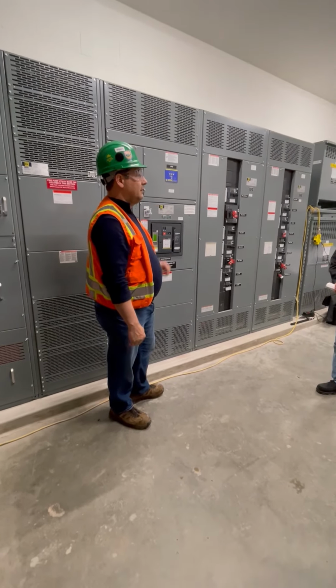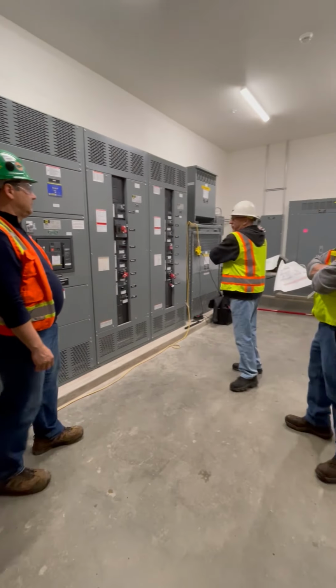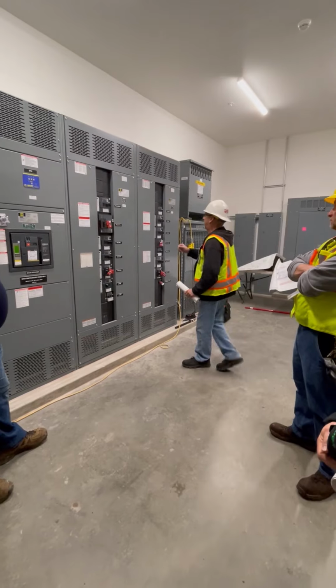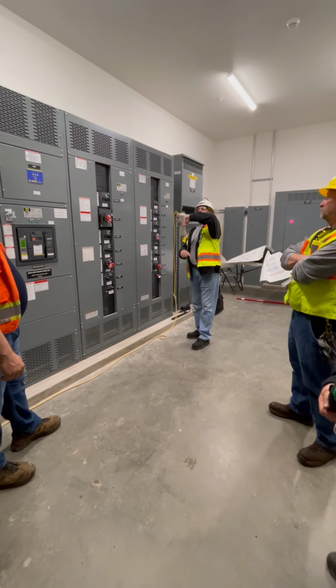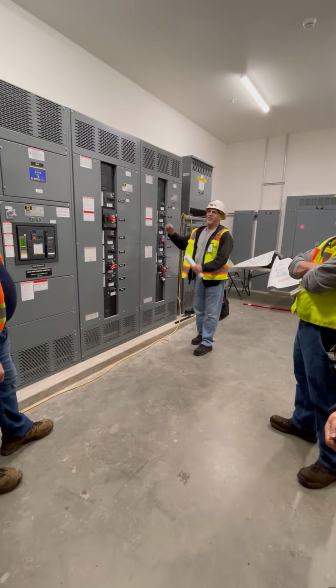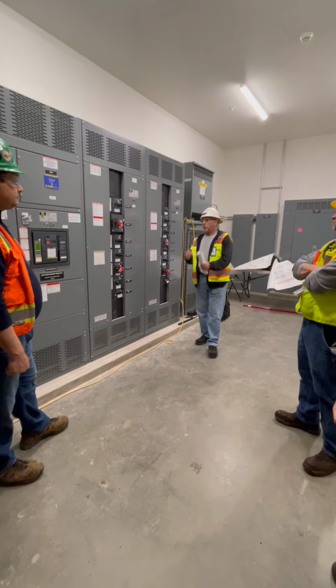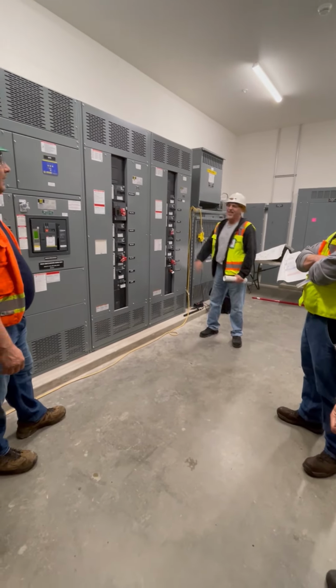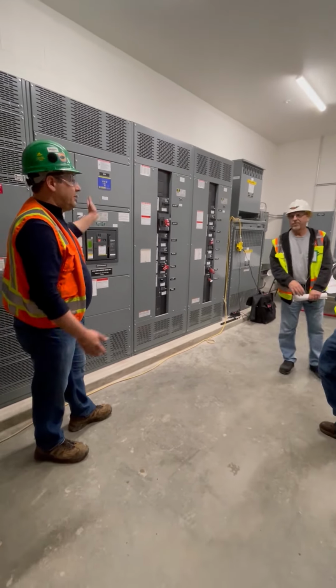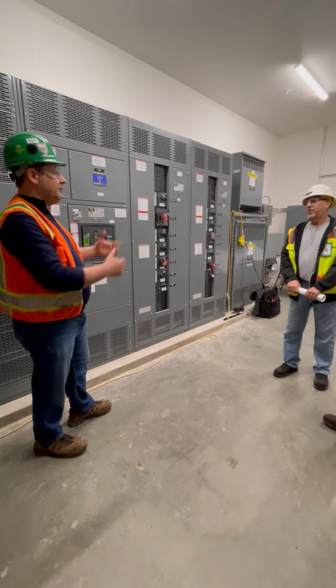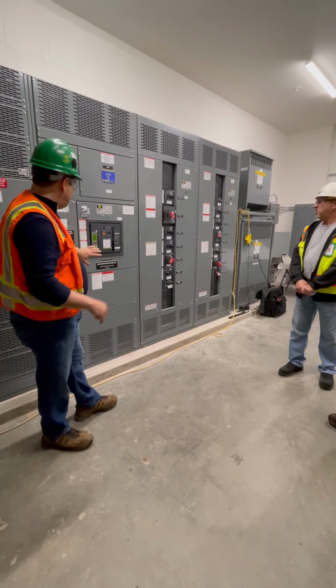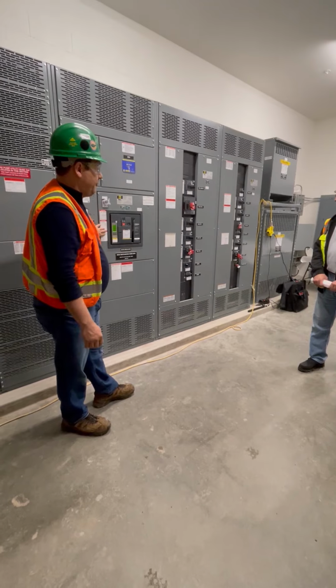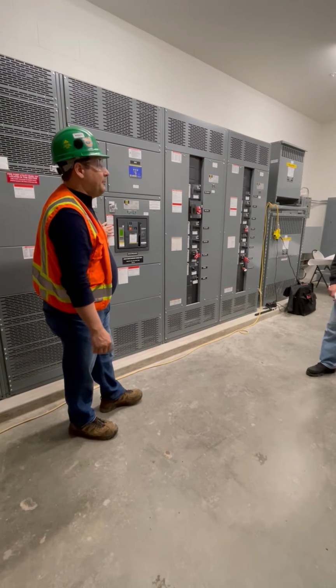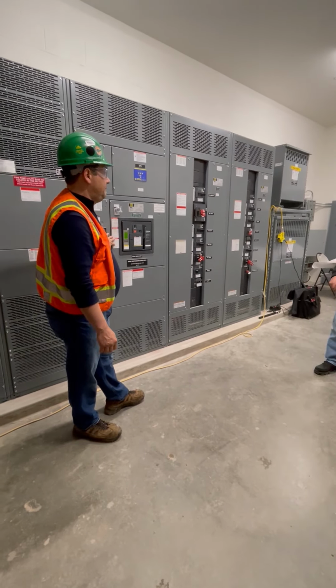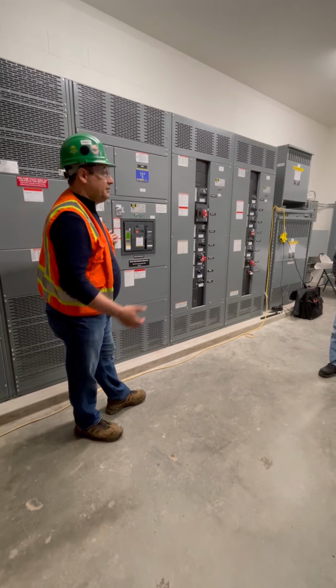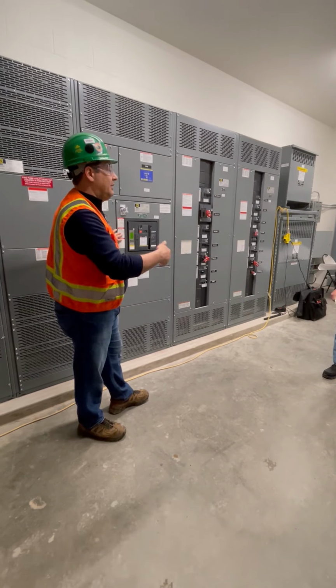It's the same thing at Fisher's Landing, like I said, we had to turn everything off downstream, turn it back on, and then one at a time, and then wait 2 minutes, and then eventually, boom, oh, that's the one. Well, at least that way you can turn the rest of it off and keep that breaker off until you find the ground fault, you fix it. But just want to mention that for operational procedures, right? If that happens, that could create some headaches, especially if it's in the middle of the school, trying to get everything back online.